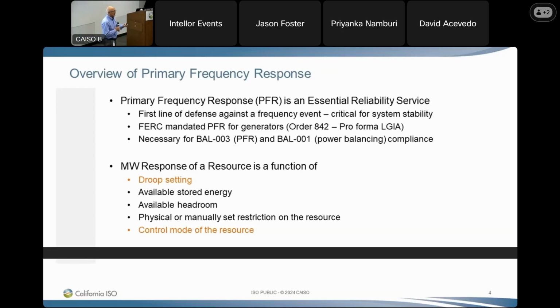If something were to happen, the automatic response from your units is the first order of response. The second order is the AGC units, then the operators, then the market. So there's a hierarchy in how we go about balancing the grid. But the automatic one, and the most important one, is really the frequency response, and it's critical that the units obligated to provide it are actually providing it.